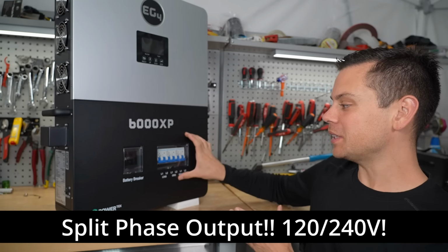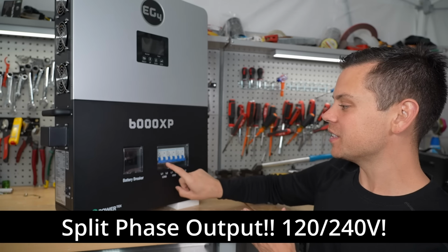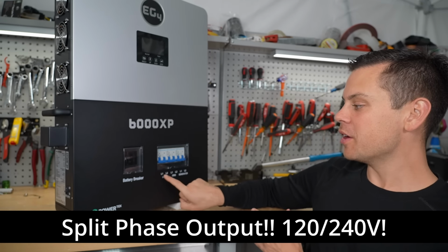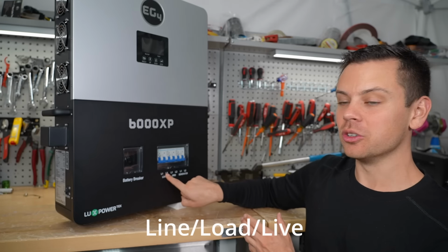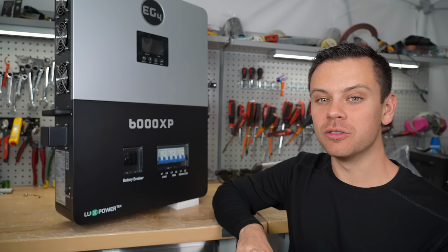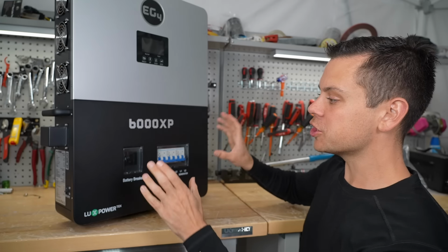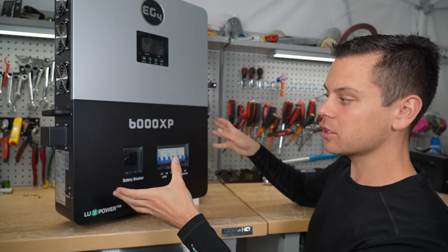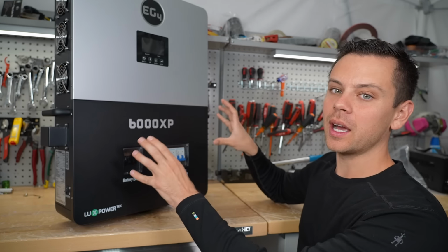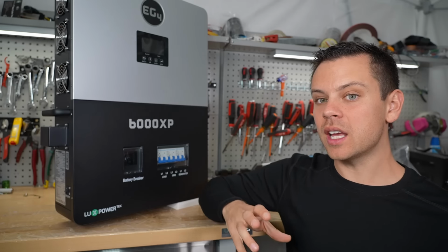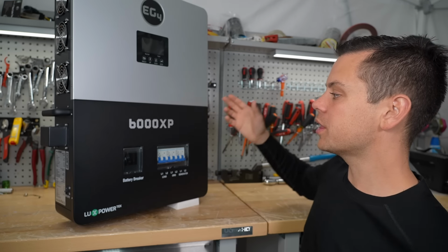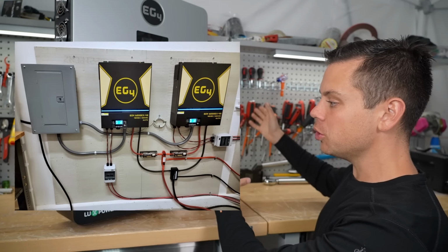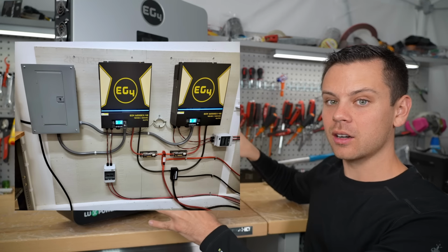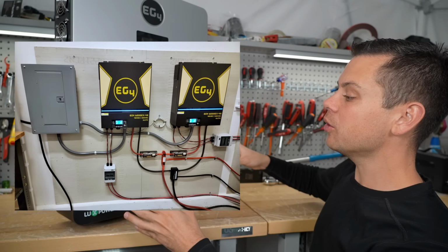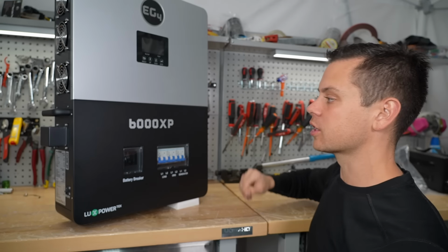Next, it has a split phase output. You'll notice on this load center with the breaker, you have a load 1 and a load 2, so you have 120 and 240 volt. That means you can run 240 volt heat pumps and other loads with this unit all by itself. If you tried to run a 240 volt load with the older models, you would have to buy 2 of them and put them into parallel with communication. Now you just hook this up on your wall and you're good to go.